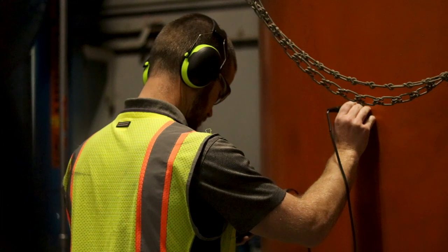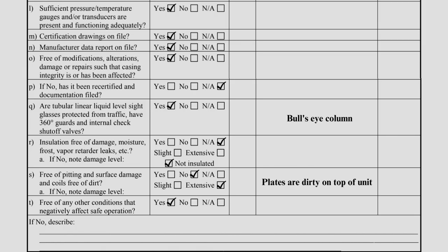While not specifically listed in the checklist, ultrasonic thickness testing can be used on a shell and tube heat exchanger to gauge the amount of material that has been lost due to corrosion. Thickness readings can be used to determine if the heat exchanger is fit for service and the remaining useful life. The checklist concludes with Item T, which serves as a catch-all for other concerns that the inspector may have observed. The area below can be used to write a description of the deficiencies. This concludes the IIAR 6 Appendix B Annual Inspection Checklist for Heat Exchangers. We have more videos on our channel about ammonia refrigeration and process safety management — feel free to check them out if you're interested.